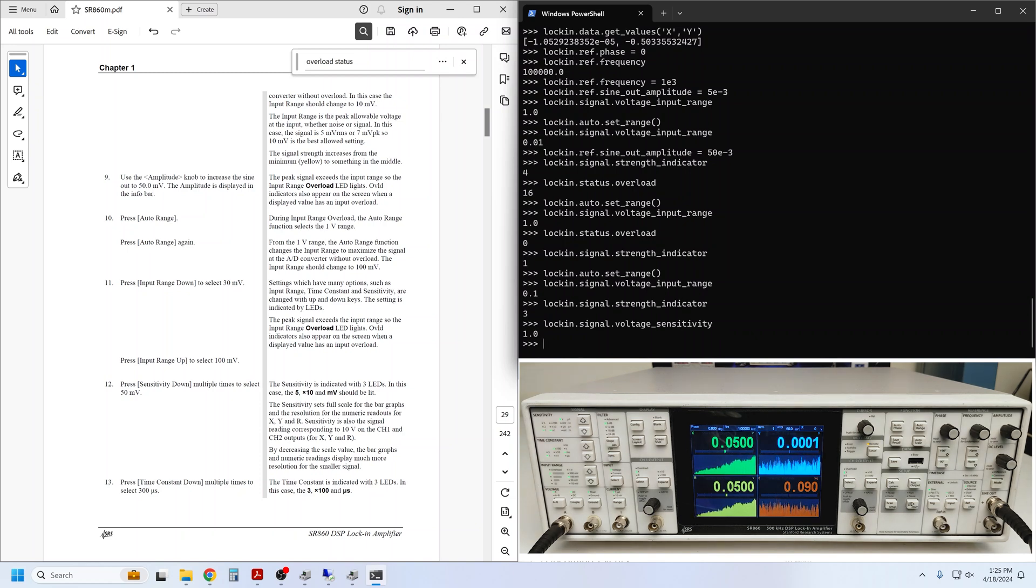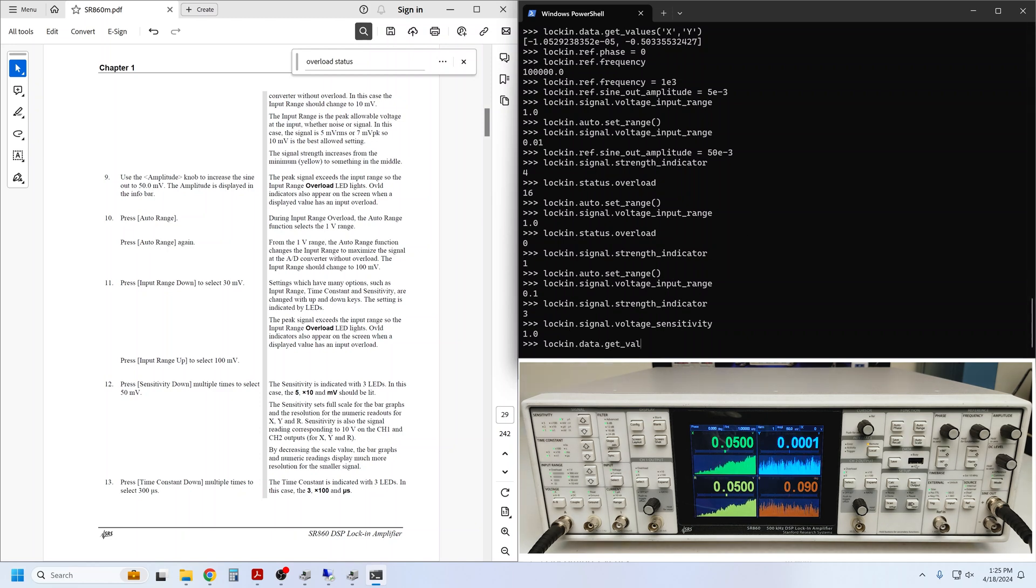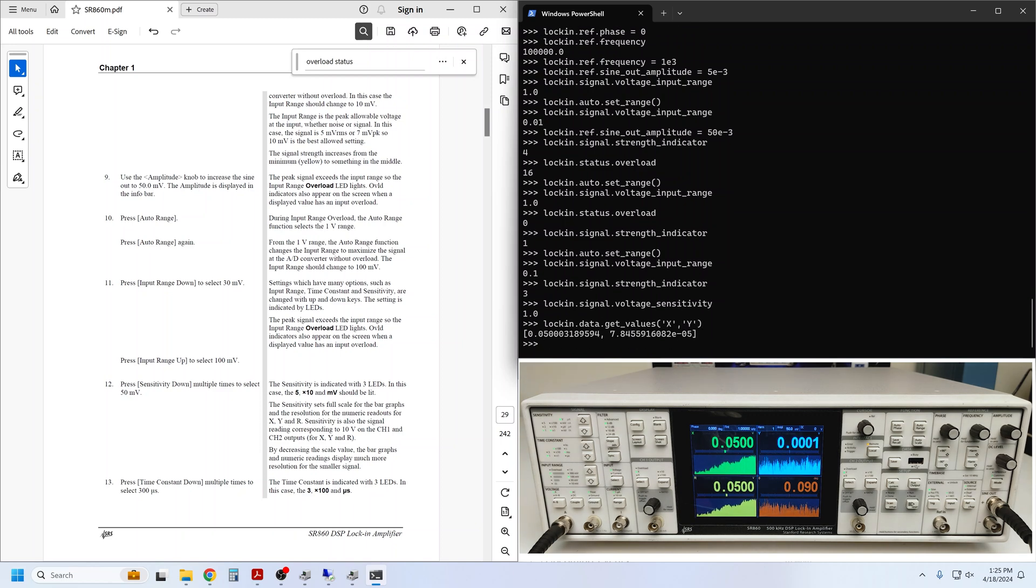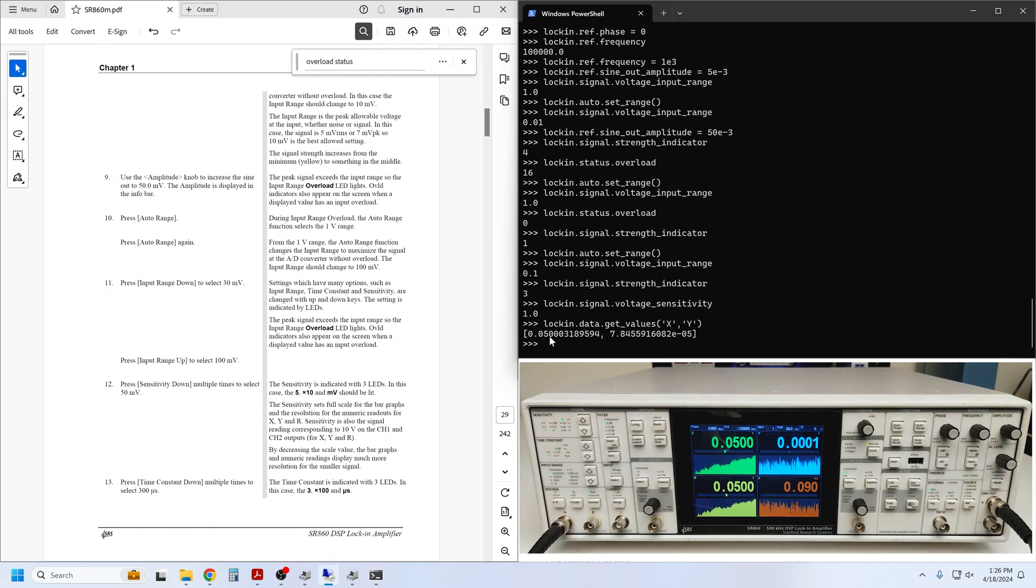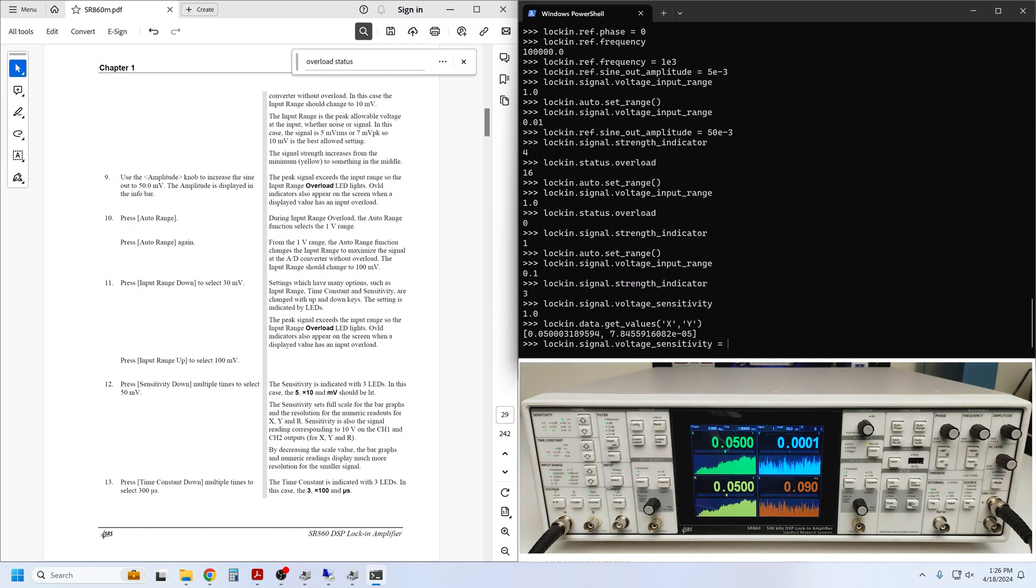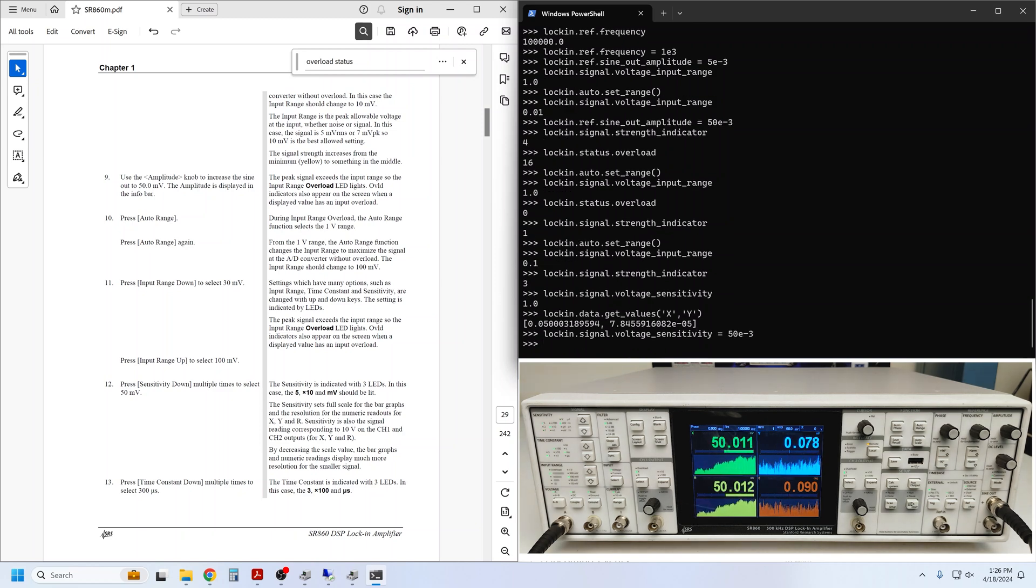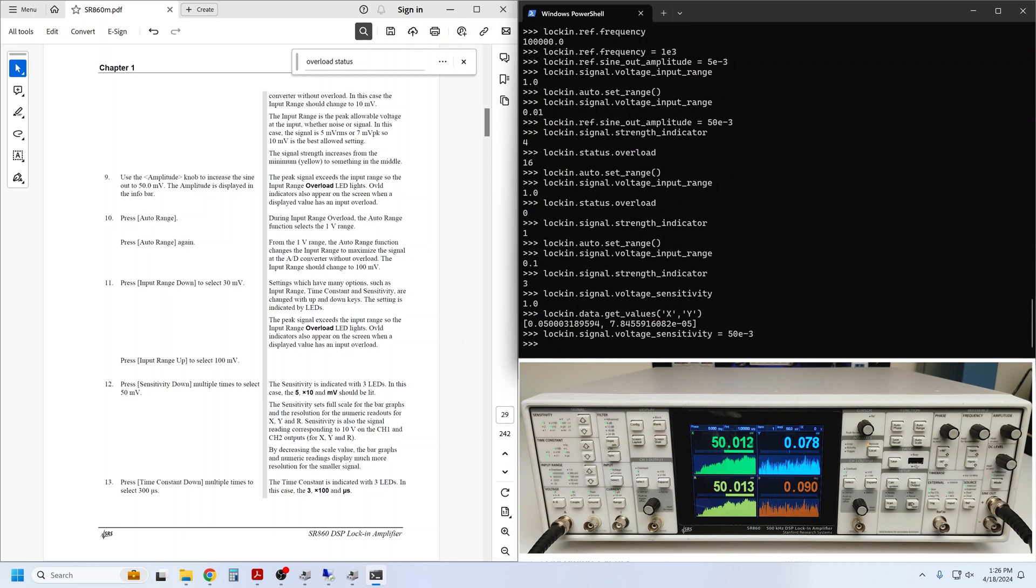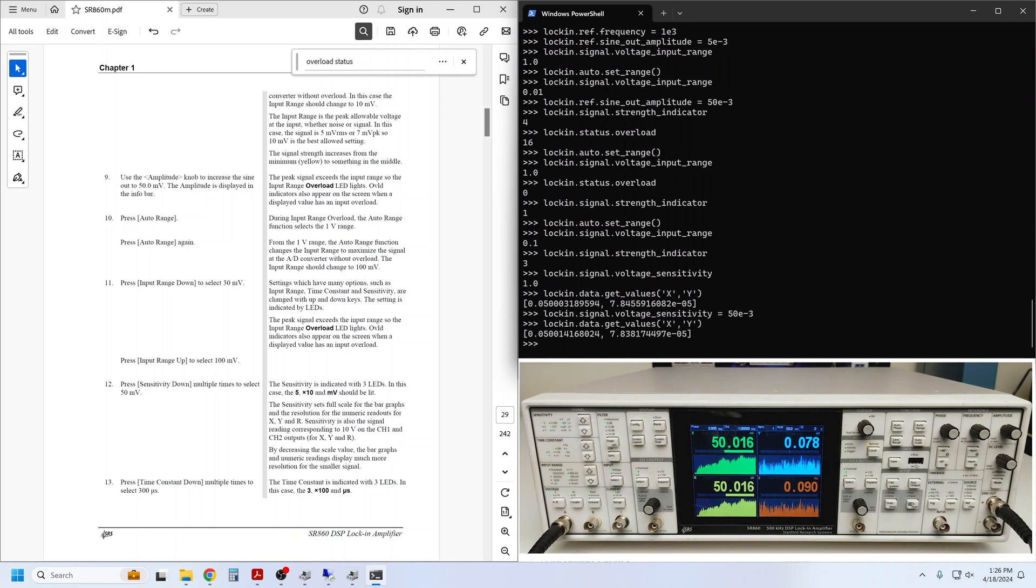Since our excitation is only 50 mV, we see that the display precision is limited by the sensitivity setting since it needs to accommodate a possible 1 volt measurement. However, this is not true for a remote query of the X and Y values. This query yields the full measurement resolution. You can see 50 mV present on the X channel. Let's see what happens when we adjust the sensitivity. The guide instructs to use 50 mV. Note that on the front panel, the bar graphs and numeric readings display more resolution now. The resolution of the remote queries, however, is unaffected.